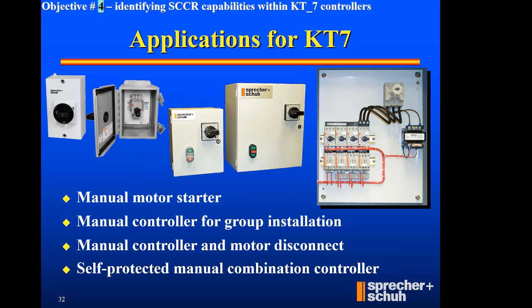You can apply it as a manual controller for group installation, meaning I've got groups of starters. However, if I'm doing group installation, up ahead of that group I've got to have some sort of branch circuit protection. Individually, I can apply it as a manual controller for motor disconnect. I can apply it as a UL 508 kind of disconnect. And then lastly, and more importantly, it can be applied as a self-protected manual combination controller type E.